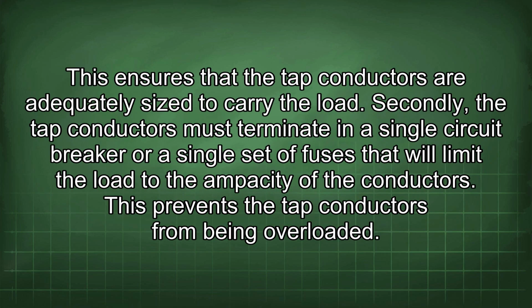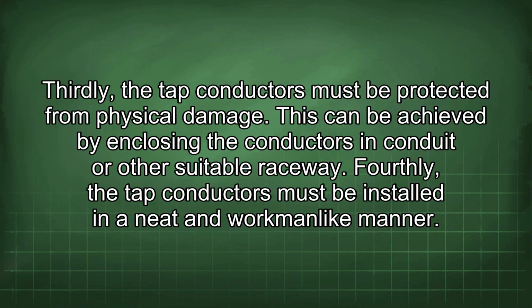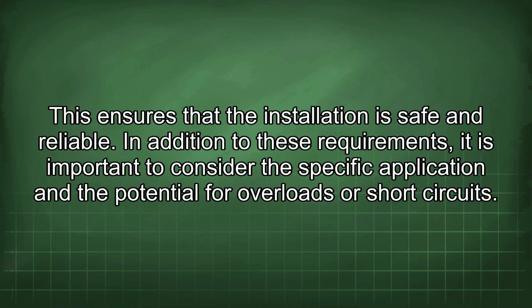This ensures that the tap conductors are adequately sized to carry the load. Secondly, the tap conductors must terminate in a single circuit breaker or a single set of fuses that will limit the load to the ampacity of the conductors. This prevents the tap conductors from being overloaded. Thirdly, the tap conductors must be protected from physical damage. This can be achieved by enclosing the conductors in conduit or other suitable raceway. Fourthly, the tap conductors must be installed in a neat and workmanlike manner. This ensures that the installation is safe and reliable.